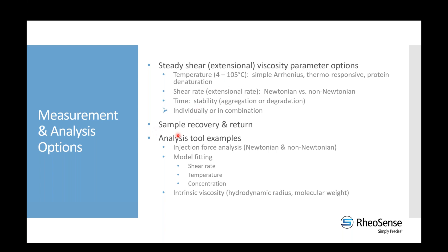We do offer the option to recover your sample from our instruments and return it to you. We can never recover 100% due to losses to internal components, but depending on the viscosity and elasticity of the sample, we can generally get back between about 50 and 90% — 90% for lower viscosity, more Newtonian-like fluids, and 50% for samples approaching a thousand centipoise or more.